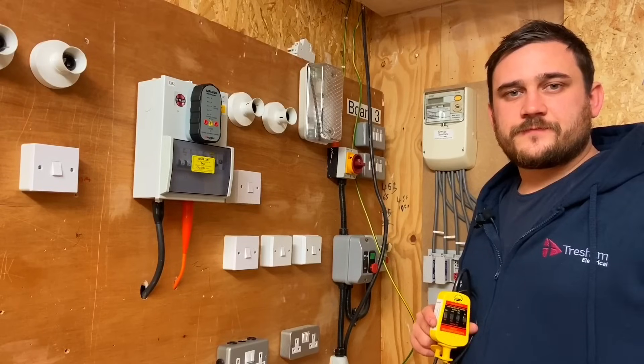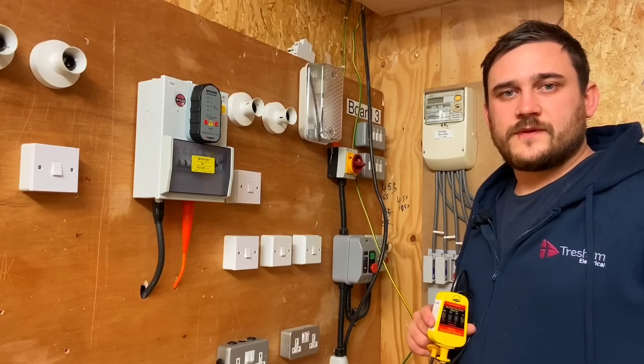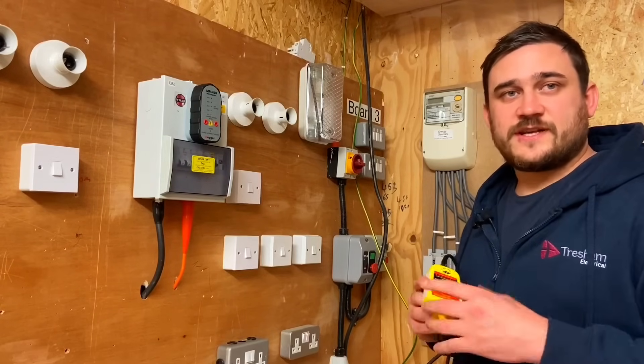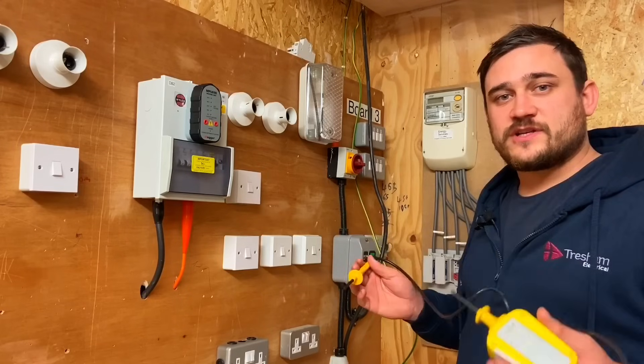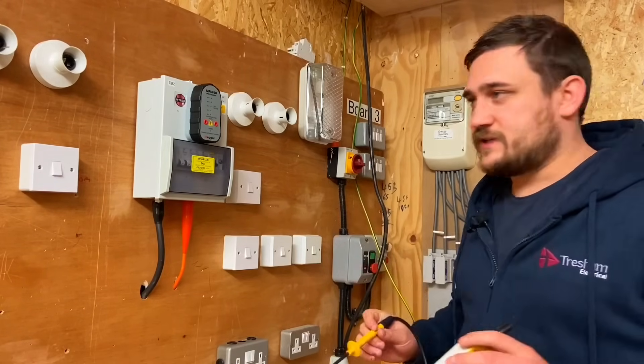All the awarding bodies and endpoint assessments require us to check our voltage indicator before using it, even for this supply polarity check. Just like the safe isolation steps, we need to prove our approved voltage indicator first. We could do this on a known source or proving unit - today we're going to do it on a proving unit.